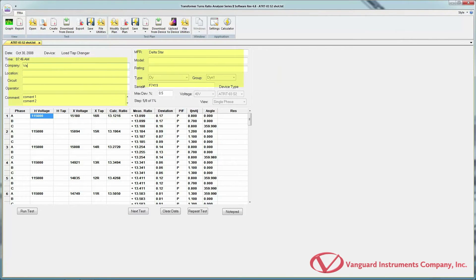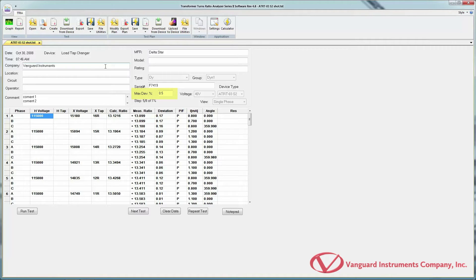Once the test record is loaded, you can modify the header information if needed. This test was performed with an ATRT-03-S2 and the test voltage was 40 volts. The max deviation percentage can be changed here — this is the tolerance value to determine if a test passes or fails. The calculated turns ratio value is compared with the measured value. If the percentage difference is greater than the max deviation percentage, the test is marked as failed; if below, it is marked as passed, shown in the PF column. You can change this value and the PF column will update accordingly.